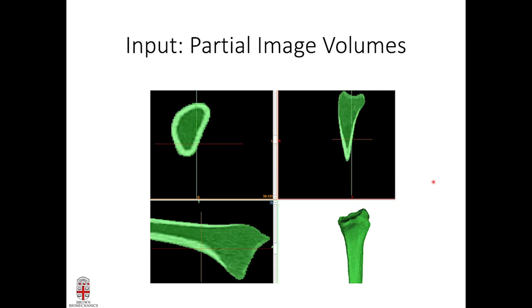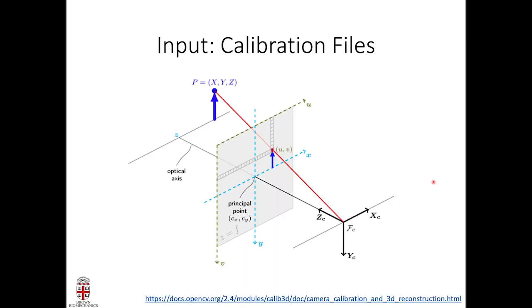We also need the calibration files. These define the space for our x-ray systems — basically where the x-ray sources are and where the x-ray image intensifiers are. Using two images, like two eyes, we reconstruct the 3D world, but we need a coordinate system to define everything relative to that.